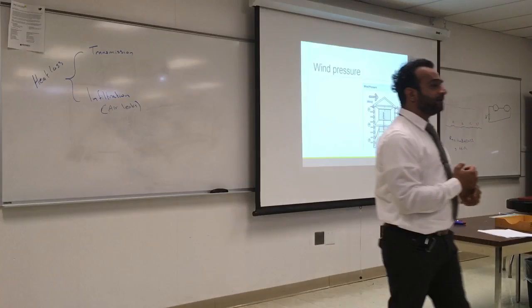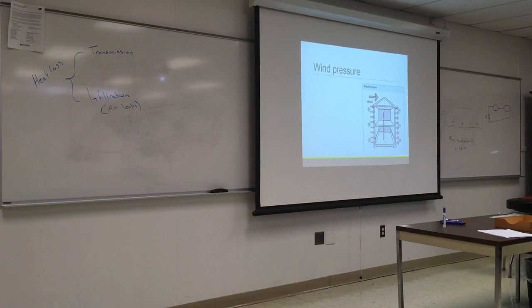How do we test for air leaks? Infrared cameras, one way. Smoke. See where the air leaks. But again with the smoke you need to pressurize the house. If there is no pressure you will never see the air migrate. So in a windy day probably it's a good day to see where the air leaks are. And you can do the blower door testing.